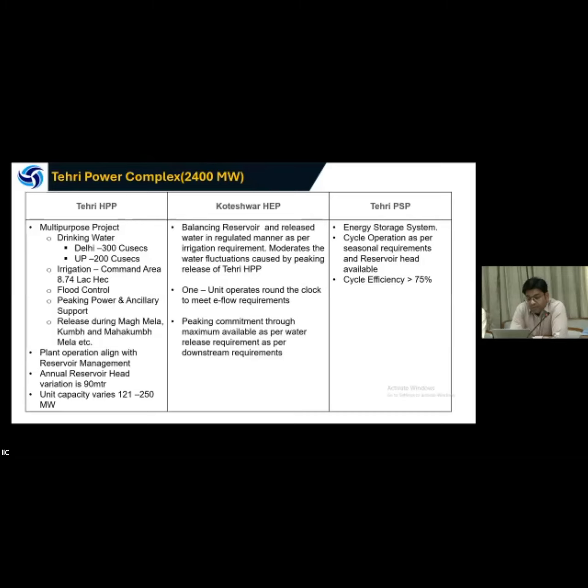The plant is operated in line with the reservoir management rule curve. Annual reservoir head variation is 90 meters. The capacity of the HPP varies from 121 to 250 megawatt. The Koteshwar is the balancing reservoir and releases the water in a regulated manner as per the irrigation requirements. It moderates the water fluctuation caused by the peaking release of the Tehri HPP. One unit of the Koteshwar HPP operates around the clock to meet the E-flow requirement. During peaking, all 4 machines are operated at their capacity.